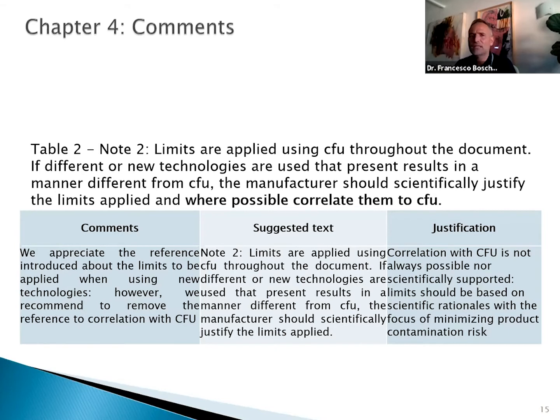But what we still didn't appreciate is the reference to the correlation to the CFU, because this may not be possible for some methods, and for others maybe not scientifically supportable. So we recommend applying the science most of all, rather than referring still to the traditional method. What we recommend is that if different or new technologies are used that present results in a manner different from CFU, the manufacturer should scientifically justify the limits applied, so without a correlation with the CFU.